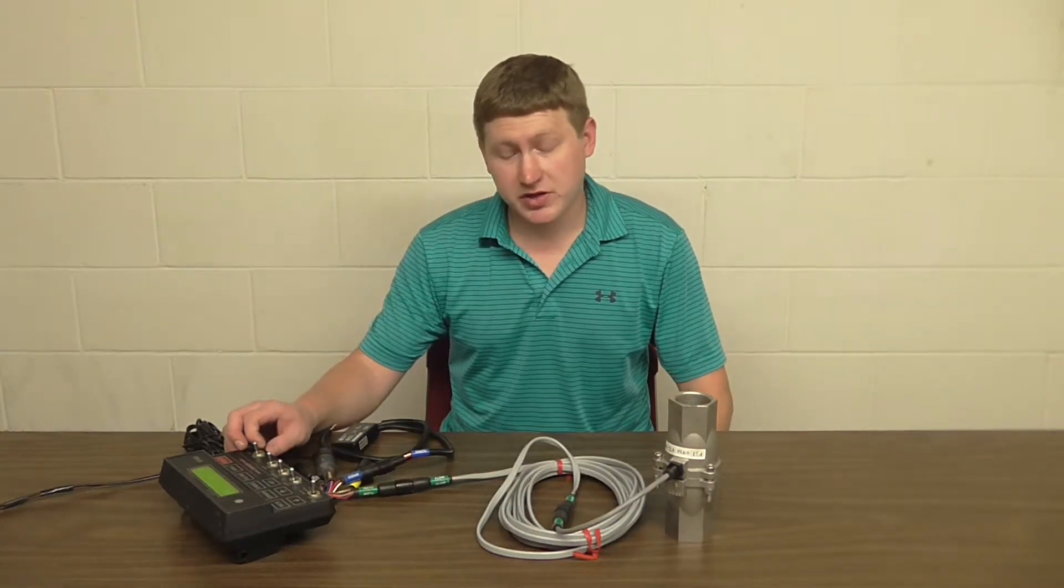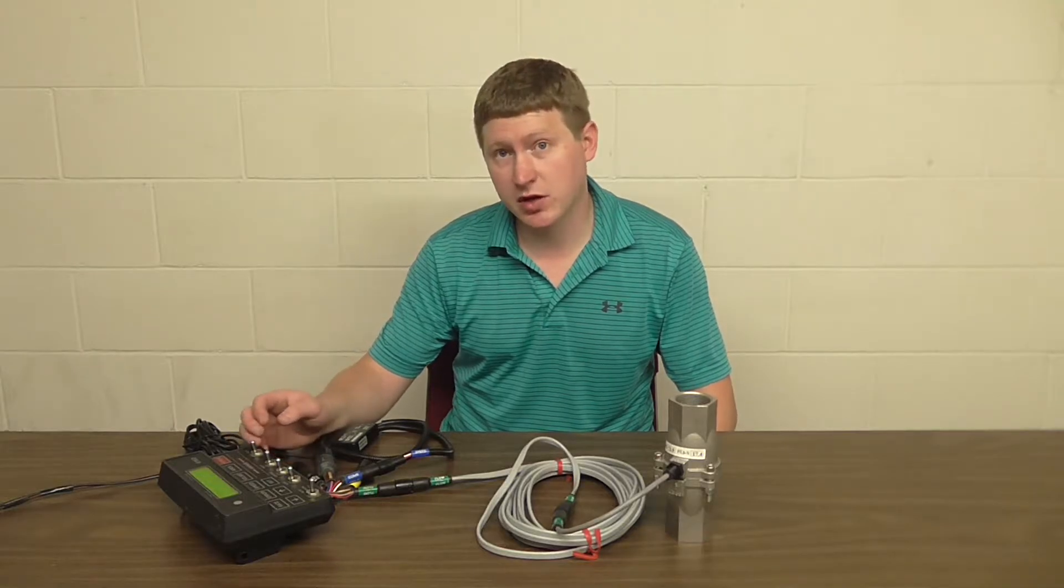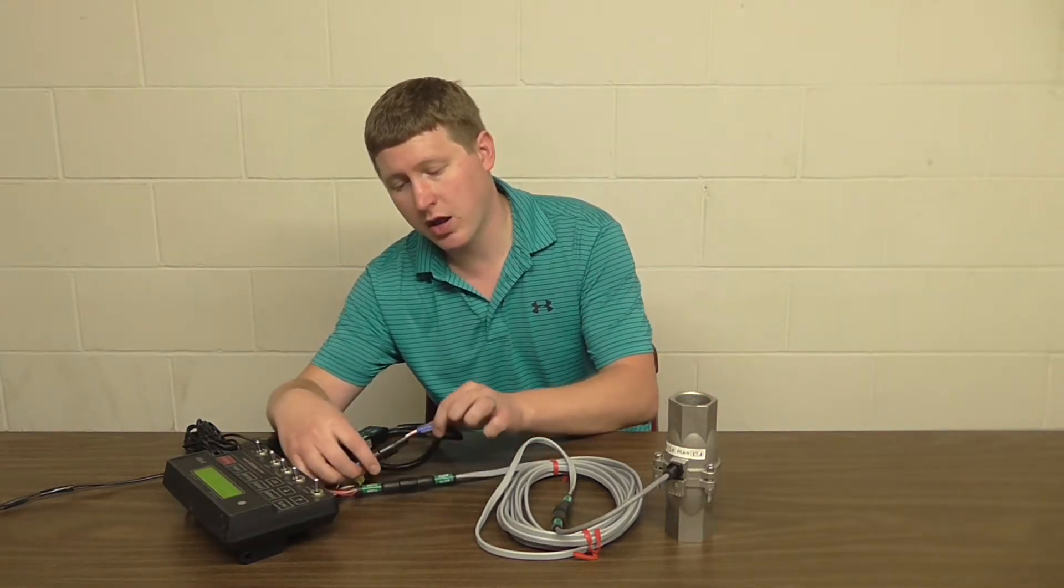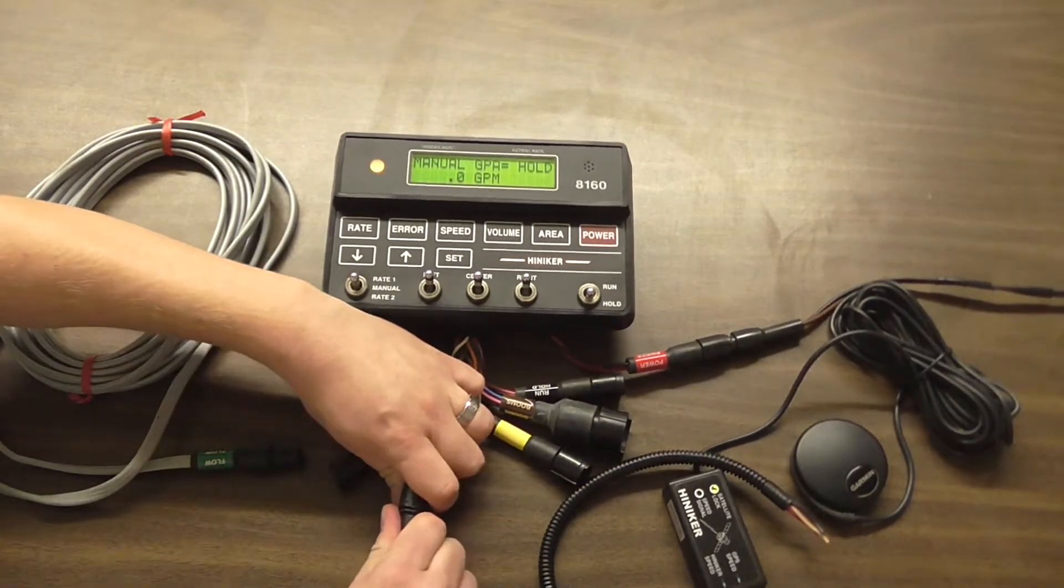The first thing we can do is actually a pretty simple test. We can check to see if the inputs on the 8160 are working by simply taking the flow and the speed cable, unplugging them, and swapping them.